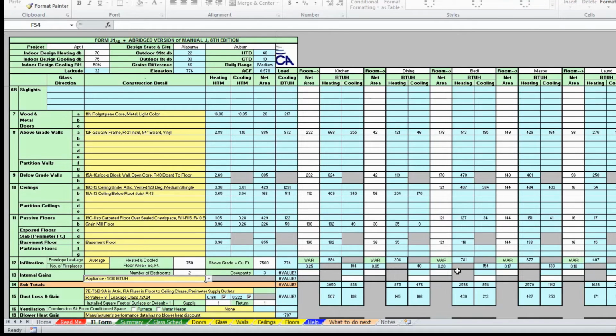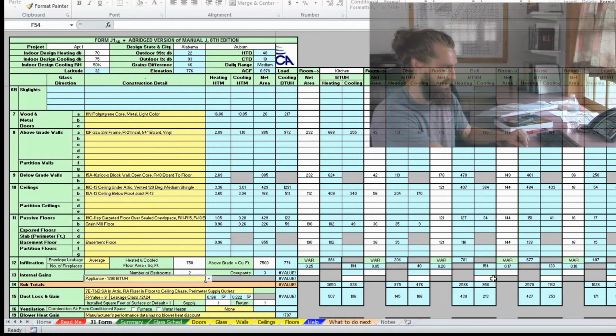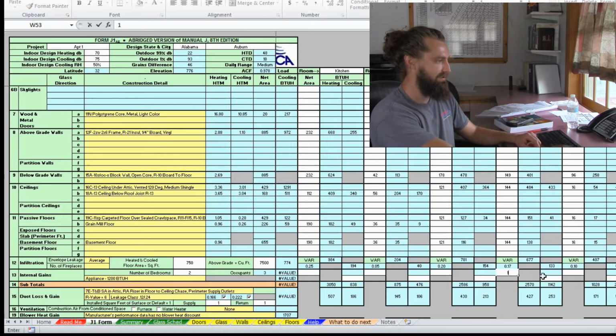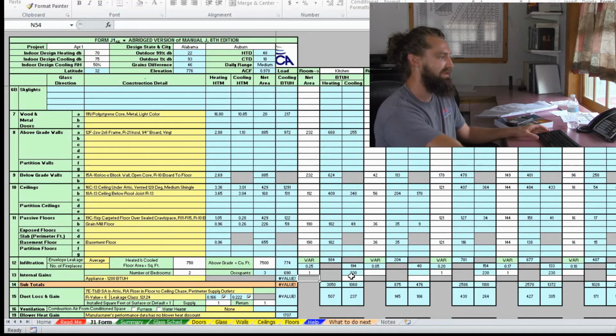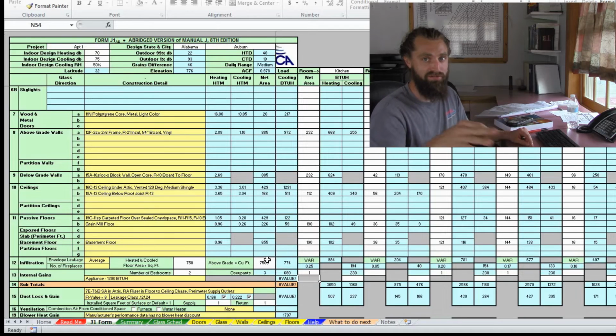So I'm going to put 1 in each bedroom. We've got 1 here, we'll put 1 in here, and then I'm going to put another guy in the kitchen, just because, why not? So now we have 3 people in this building, giving us a cooling load of about 700 BTU per hour just for people being in there, sleeping and eating and everything like that. If you were doing your manual N and looking at a commercial building, this is right here where you'd have to assign what these people are actually doing.